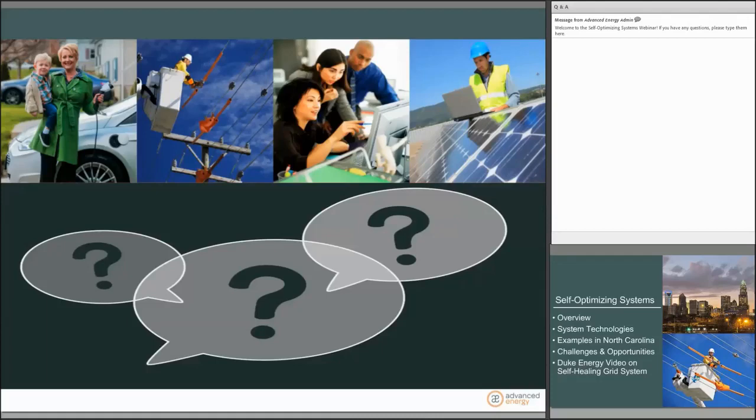Yeah, that's another good question. So our North Carolina utilities are looking carefully at how their system is designed and built today with the traditional grid. And they've looked at the potential segmentation and feel that this is a reasonable target. So, for example, there are parts of their territory that are very rural and maybe only served by one substation or transformer, could have 2 feeders going in opposite directions, and it's just not economical to add a substation or transformer or many miles of circuit. So for these customers, the utilities are adding just the ability to switch remotely and some segmentation. So there are benefits, just not the full self-optimizing.